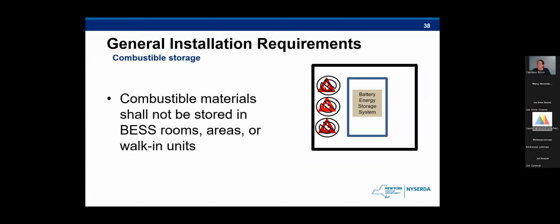Once again, a pretty common sense requirement: combustible materials should not be located within 3 feet of cabinets containing energy storage systems or within a walk-in unit or room. Having a fire on the exterior of the system could possibly cause the batteries to fail and lead to a fire in the energy storage system. So it's usually best to avoid any potential fires close to an energy storage system.